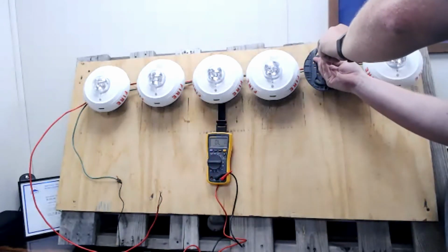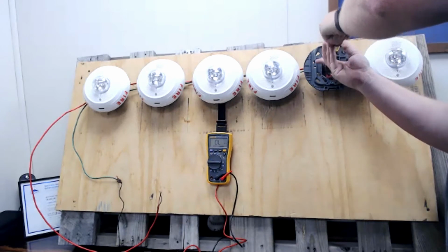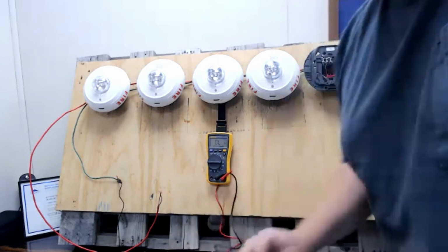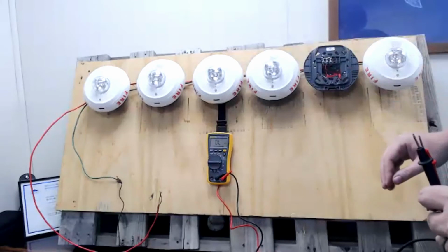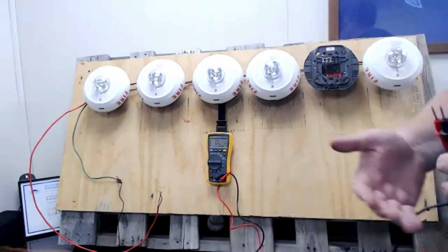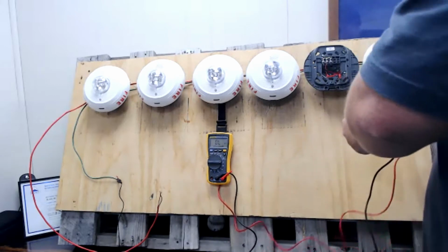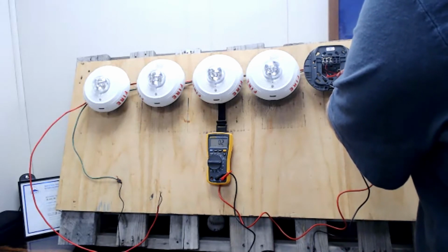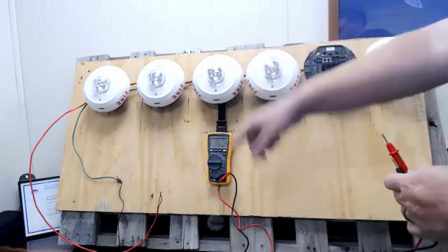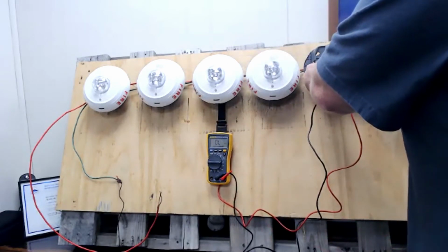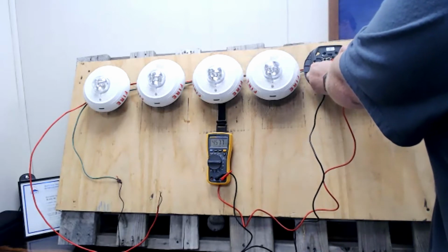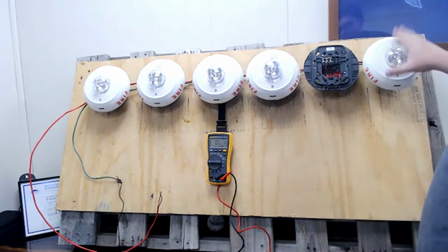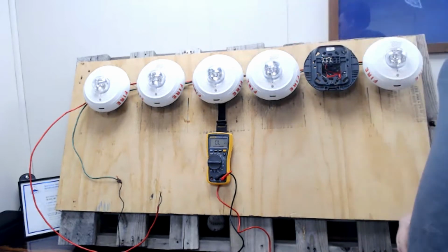Oh, I forgot to verify my repair for y'all real quick. I'm going to have to do some double work because I was talking and not thinking about what I was doing. All right, so even though I found an open circuit, I want to verify right here at this device that I have fixed the problem, that there's not another problem on the circuit. So I'm going to put my meter on. I'm still on the resistance setting. I'm going to check right here. And I see 0.2 ohms, that's the hard short. That goes back to my home run. And then here, I'm going to check. I see 4.577. That's going to be my end-of-line resistor because I have a 4.7K end-of-line. So that's what I want to see. I can see my resistor here, and I can see my home run on the other side of the circuit.